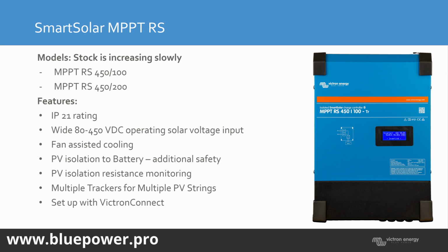So it's got PV isolation resistance monitoring as well, and you program it with Bluetooth from VictronConnect. These units communicate on CAN, so you can add up to 25 units on a string on one installation. Or if you've only got one unit, it's also got a single VE.Direct port, if you want to communicate via VE.Direct. But via VE.Direct, you don't have the ability to change the settings remotely via the server.